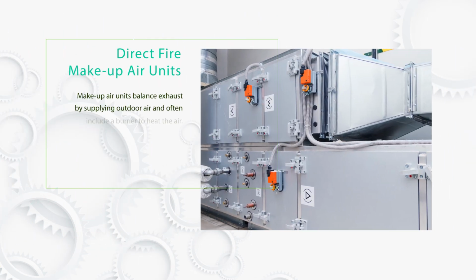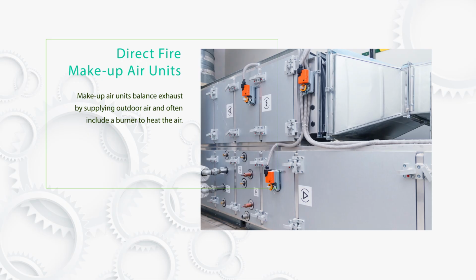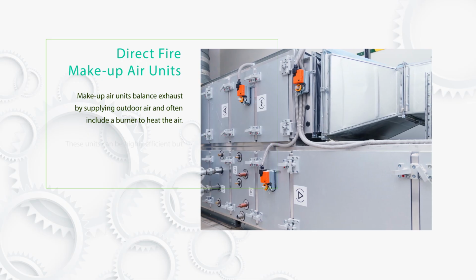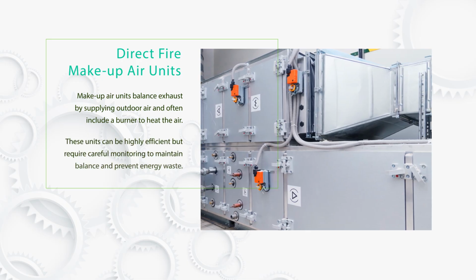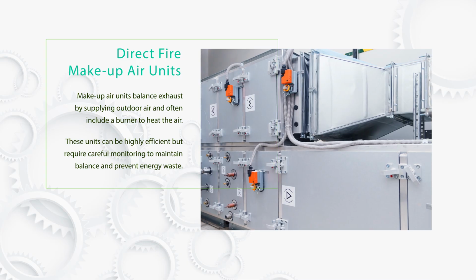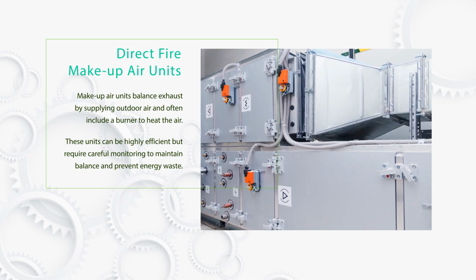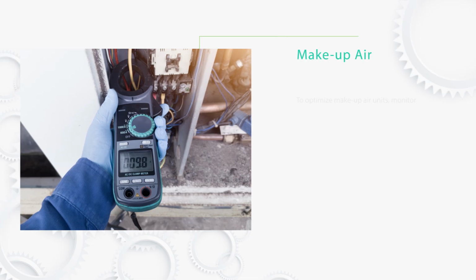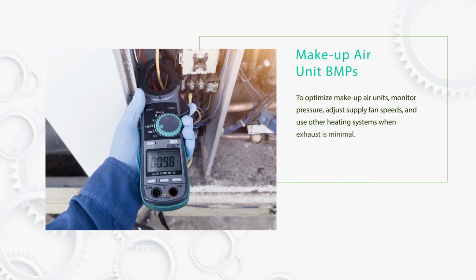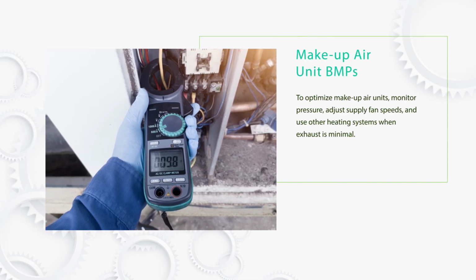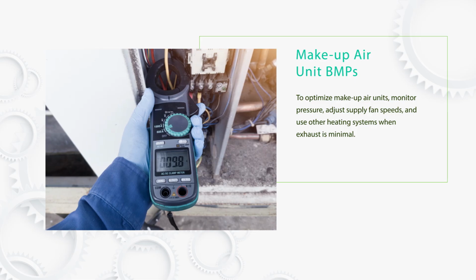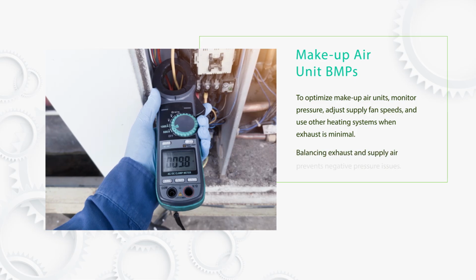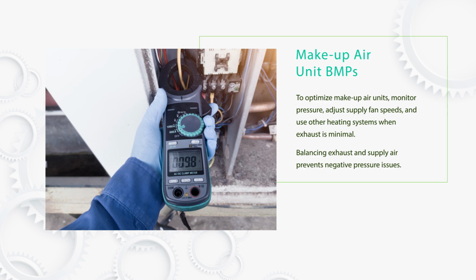Makeup air units balance exhaust by supplying outdoor air and often include a burner to heat the air. These units can be highly efficient but require careful monitoring to maintain balance and prevent energy waste. To optimize makeup air units, monitor pressure, adjust supply fan speeds, and use other heating systems when exhaust is minimal. Balancing exhaust and supply air prevents negative pressure issues.